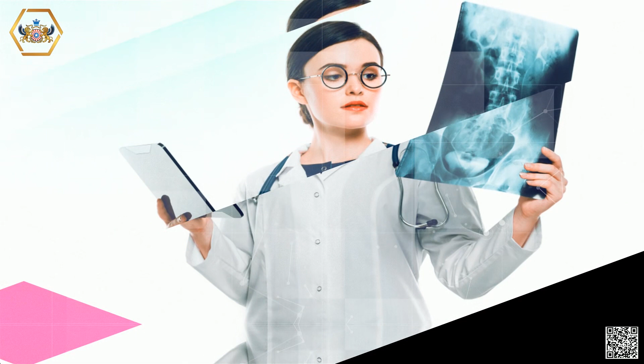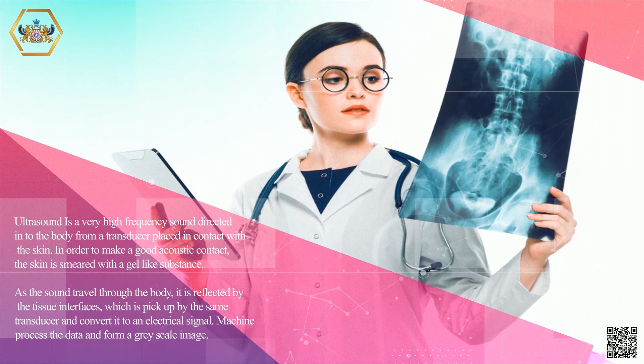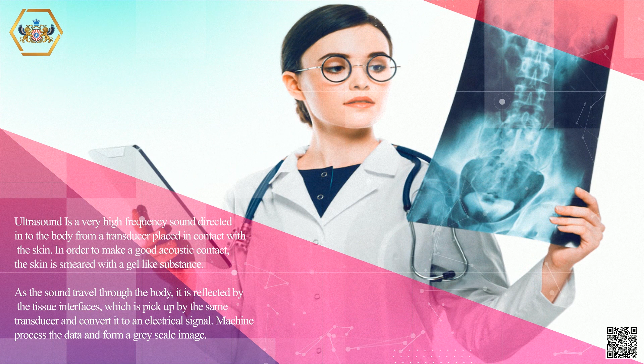Ultrasound is a very high-frequency sound directed into the body from a transducer placed in contact with the skin. In order to make a good acoustic contact, the skin is smeared with a gel-like substance. As the sound travels through the body, it is reflected by the tissue interfaces, which is picked up by the same transducer and converted to an electrical signal. The machine processes the data and forms a grayscale image.